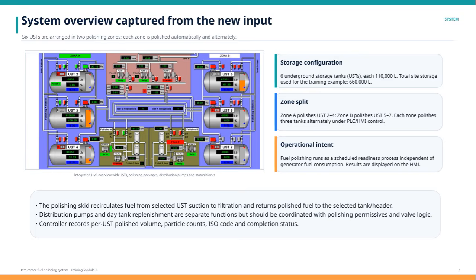Fuel polishing is designed to run as a scheduled readiness process, which means it operates independently from the generator's fuel consumption. The entire operation is monitored and controlled through an integrated human-machine interface, or HMI, that provides status updates on the USTs, polishing packages, distribution pumps, and overall system status. The polishing skid pulls fuel from a selected tank suction, passes it through filtration, and returns the polished fuel back to the tank or header.